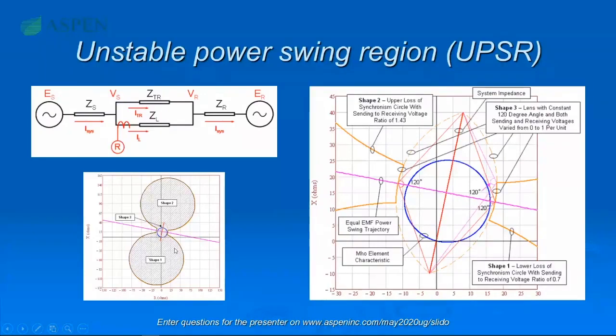When you click OK, the dumbbell shape will appear for the distance relay, and a threshold will appear on the overcurrent relay dialog window to show where the tripping should and should not be. The trip should not be within the last section on the overcurrent window, and there's also a horizontal line showing a 15-cycle time limit — meaning PRC-26 lets you treat this with a delay, but not instantaneously. On both pictures shown, your relay will pass: on the left, the zone 1 tripping characteristic is not encroaching the dumbbell shape, and the instantaneous overcurrent is not encroaching that threshold.